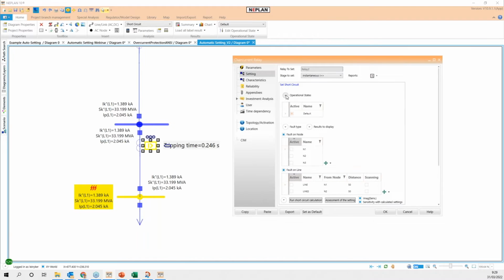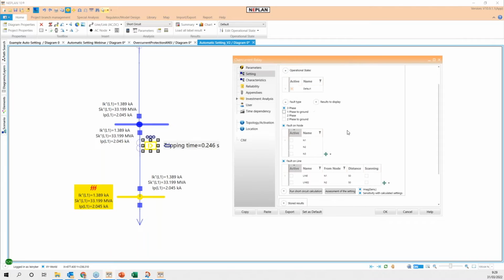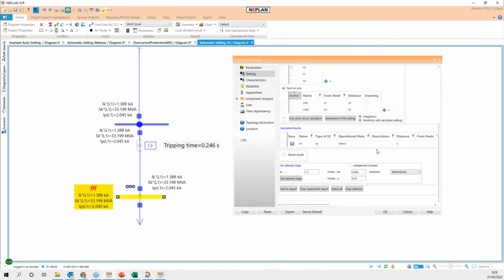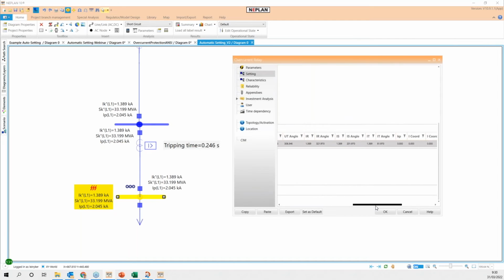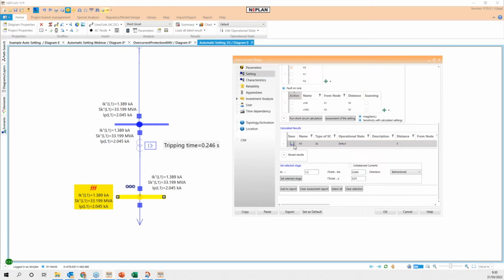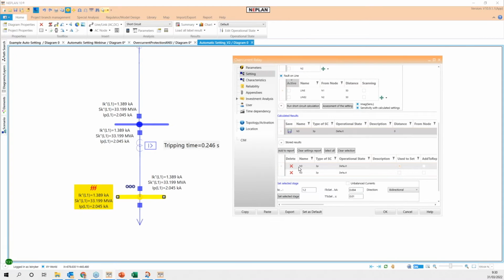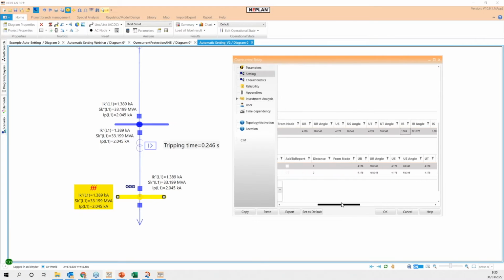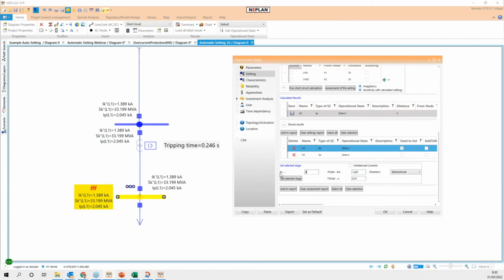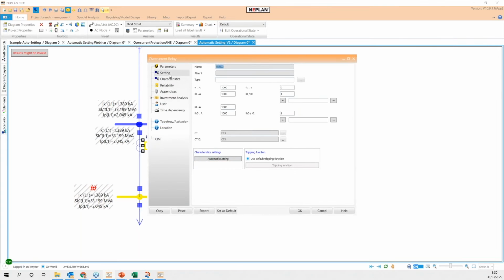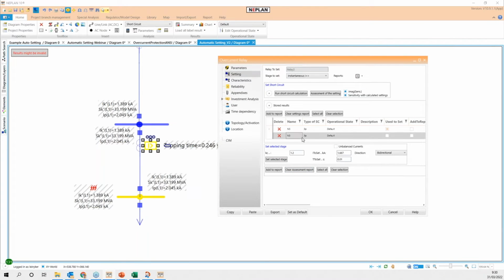How can we set that? We will set, for example, a three-phase fault. We can set a short circuit level in node number 3, and let's run the simulation for that node location. We can see the impact of having the short circuit at that node. That means that if we have the short circuit in this location, the current is around 1.4 kiloamps. We can use that short circuit level, and we can set some criteria. For example, what happens if we set the instantaneous unit at 50% of the short circuit level?